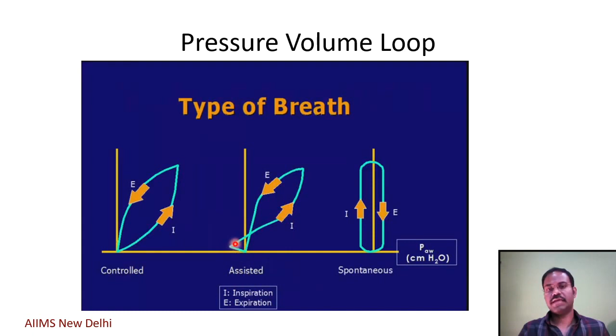Now let us examine closely how the PV loop will vary with change in the compliance. The central green waveform suggests the normal PV loop. Here the compliance is derived basically from the slope of this PV loop. So compliance basically is change in the volume with change in the pressure, delta V divided by delta P. The unit is ml per centimeter of H2O. So the slope of this PV loop will suggest how the compliance is.